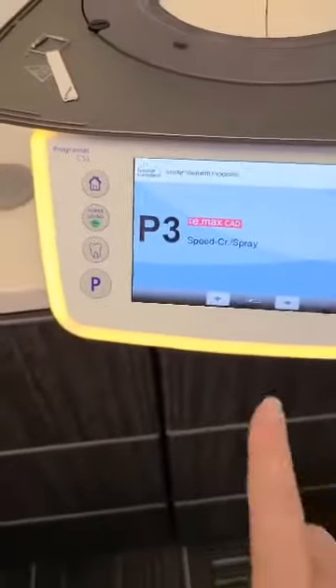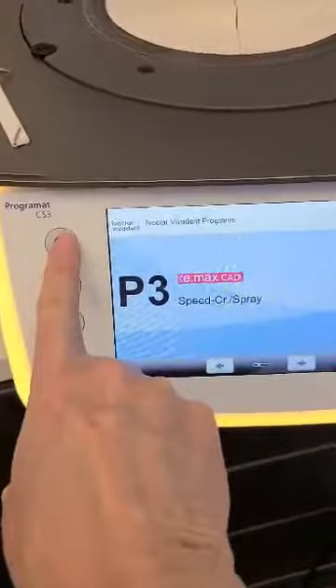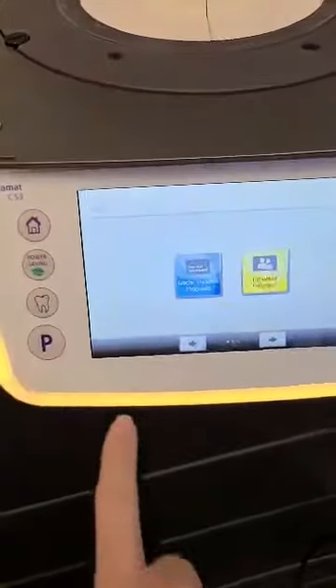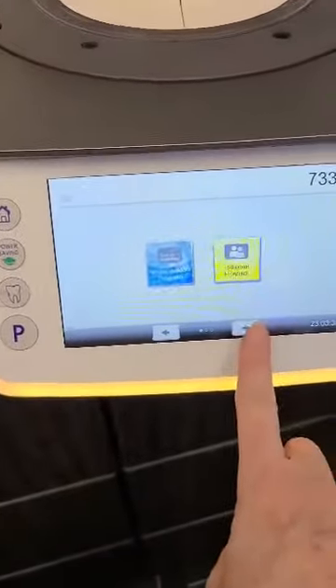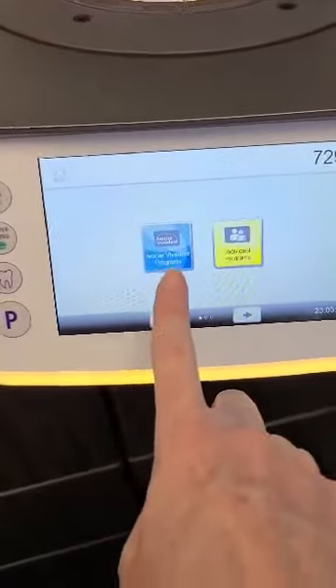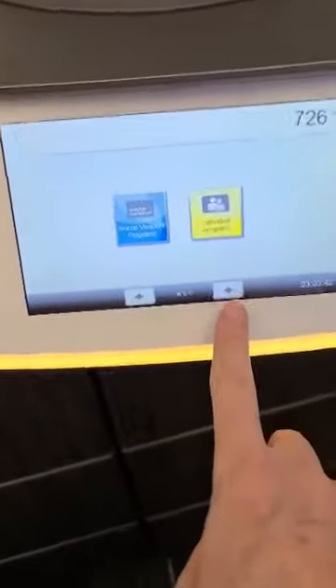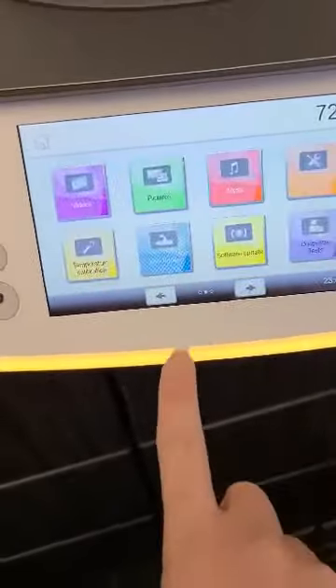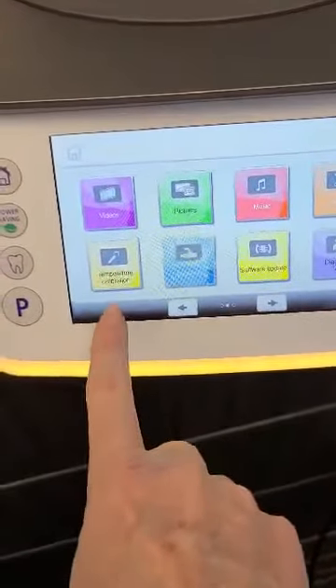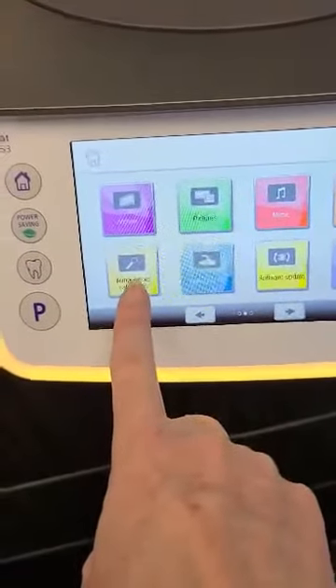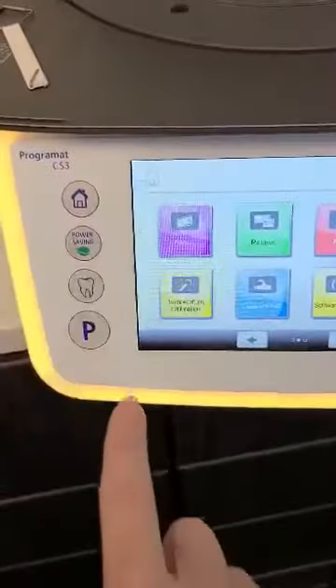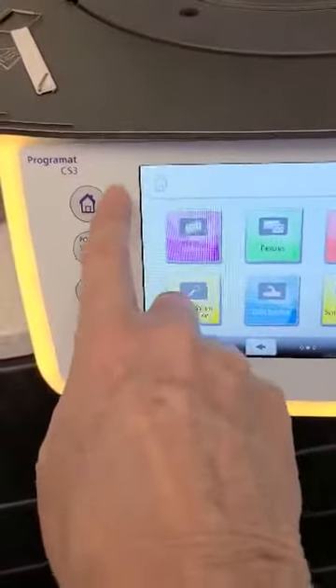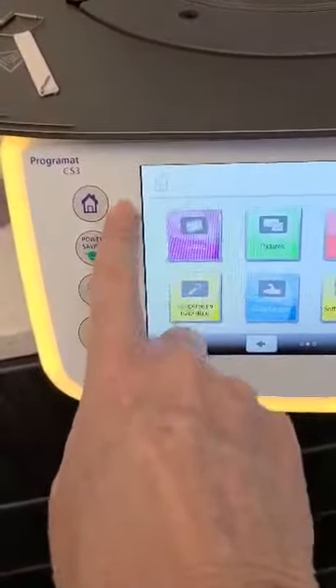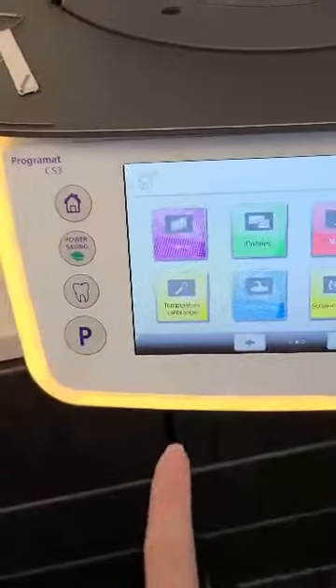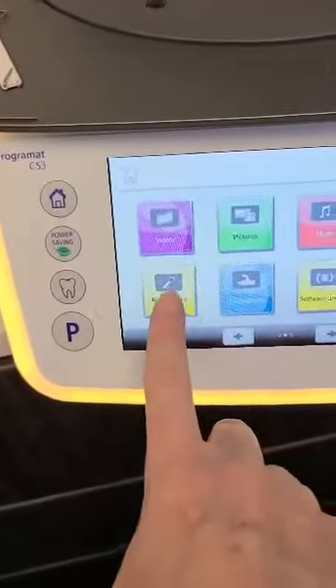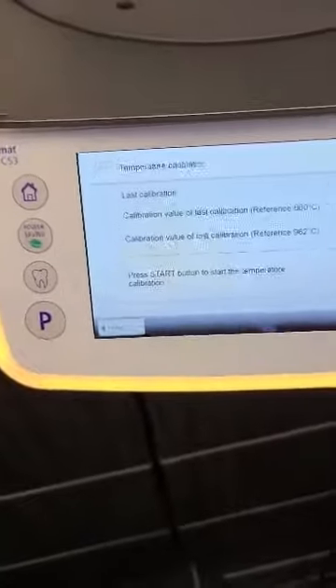So on this CS3, I'm looking for this home button here. And again, there's your program buttons that you're used to, the individual programs and an arrow forward. There is a separate tab just for temperature calibration. If you have a CS2 oven, you're going to look for that little screwdriver or wrench looking button, and you'll have to arrow forward until you can see temperature calibration for the CS2.